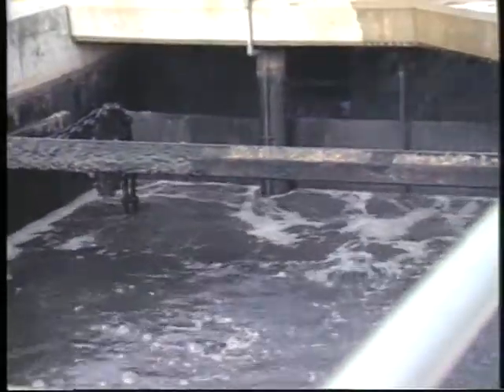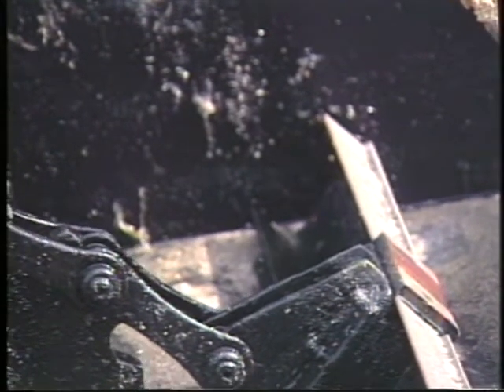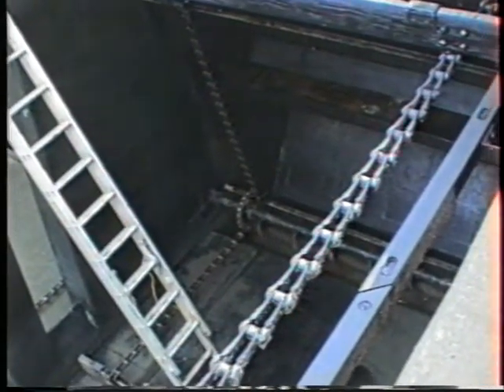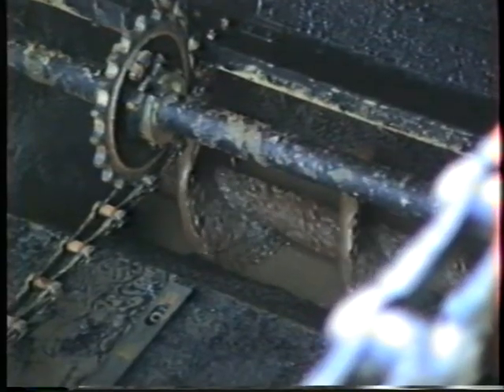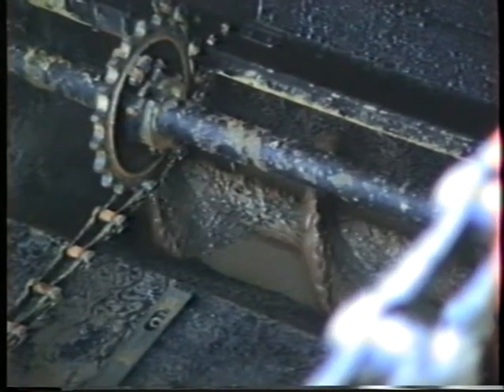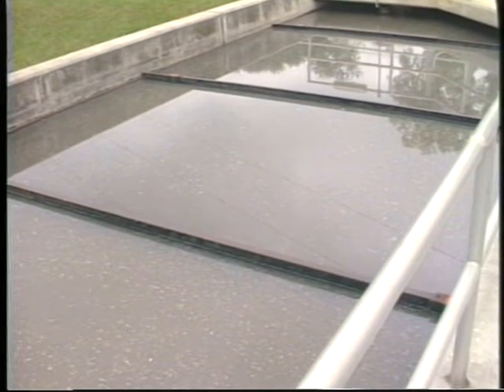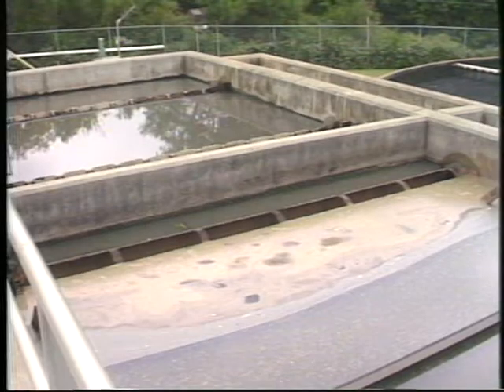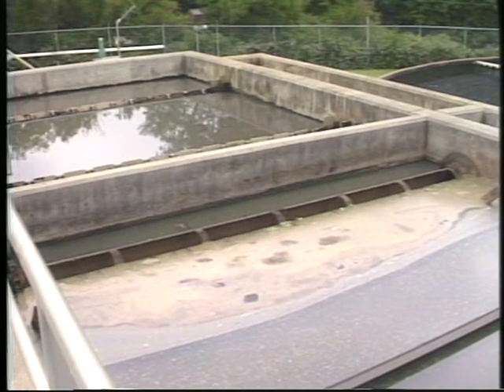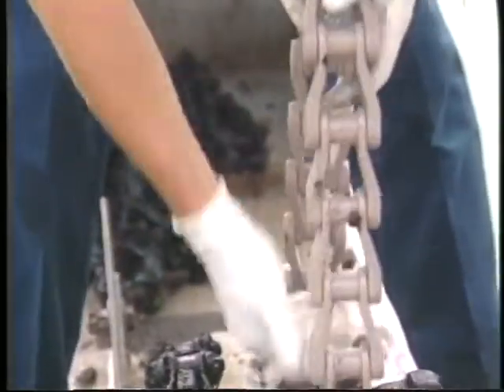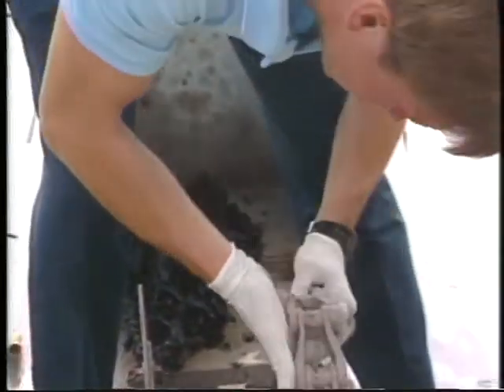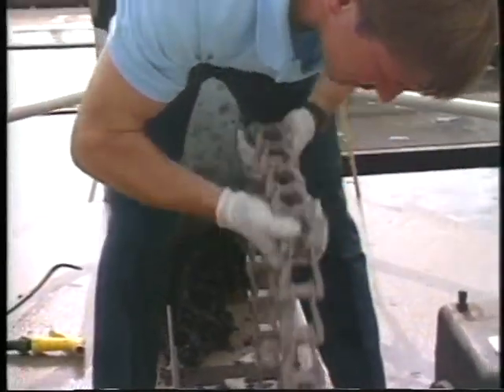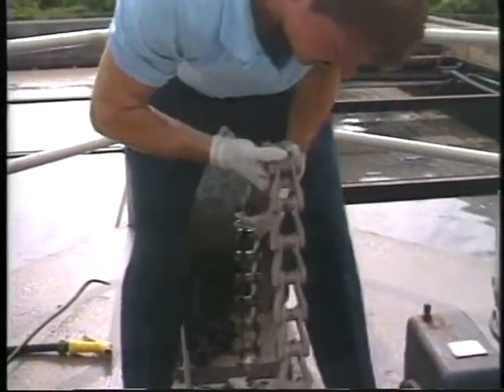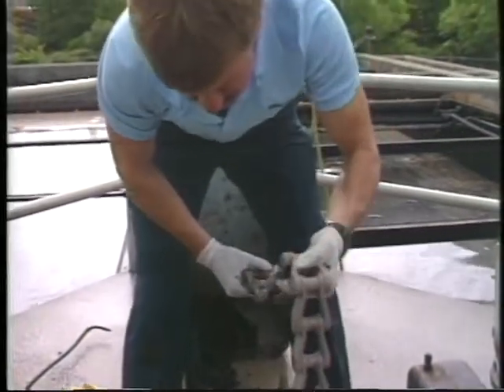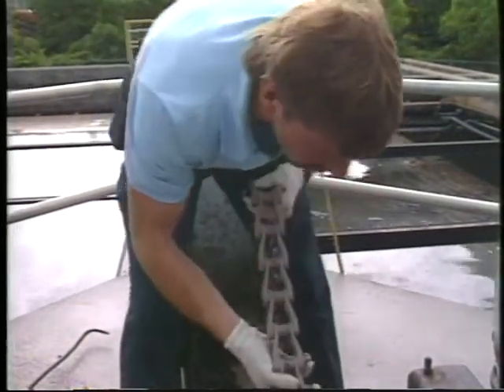The collection mechanism is a continuous chain and scraper assembly that travels slowly while scraping the settled biosolids into a hopper on the bottom of the clarifier. The mechanism then travels to the surface where it collects and moves the floatable solids to the scum removal device. In most cases today, the chain on the collection mechanism is made of a strong plastic material, and the flights or scrapers are made of fiberglass. Even the sprockets being used today are non-metallic.